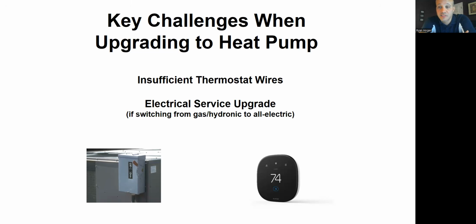The electrical wiring should be fine in almost every application, because the AC unit outside probably needs the same size gauge of wire and the same size circuit breaker as the heat pump you're going to put in. In fact, the heat pump might be even a little bit less just because it's way more efficient than the old AC that you took out. Once in a while, you could have a heat pump model that needs a larger wire gauge than the AC would. You just have to look at those kinds of things. But like 99% of the time, all of your existing high voltage wiring can stay. The thermostat wiring is where you have to make the change.